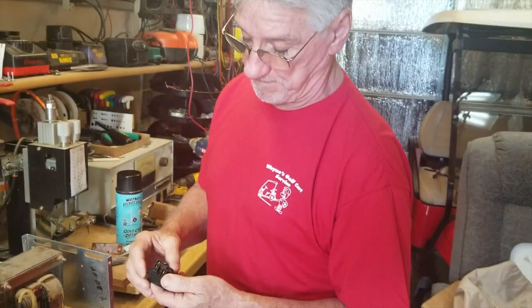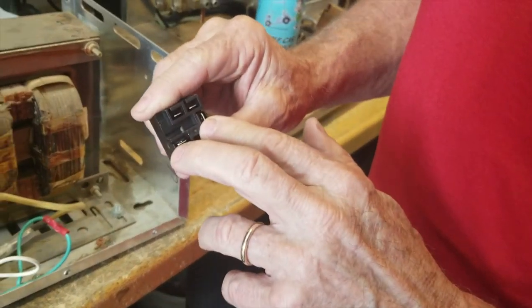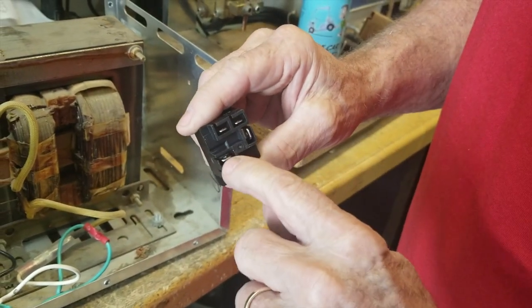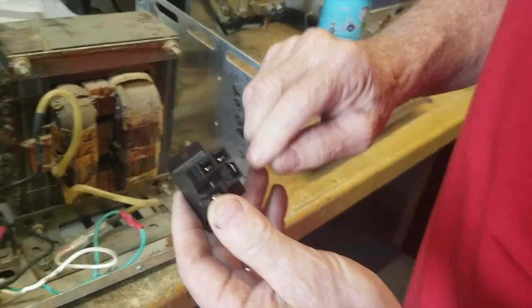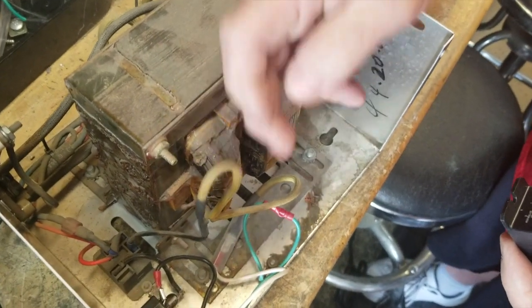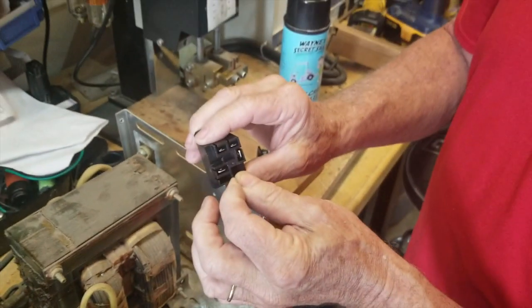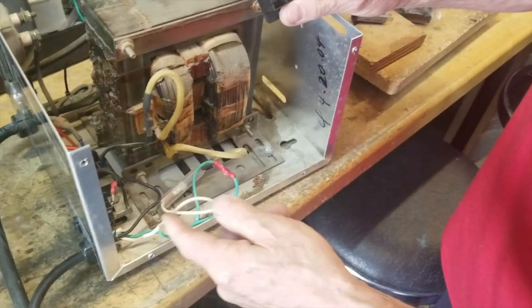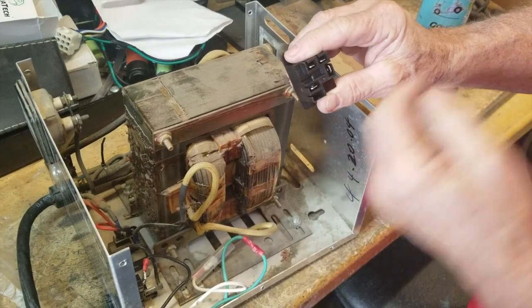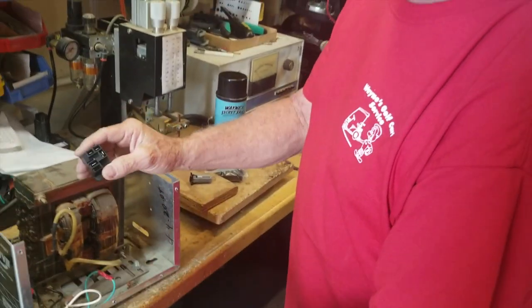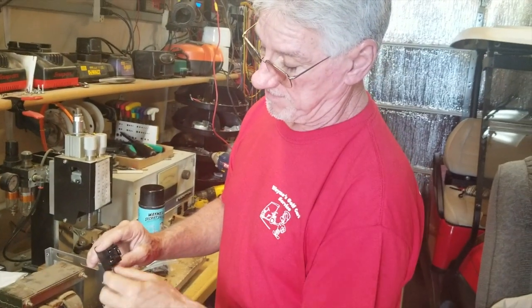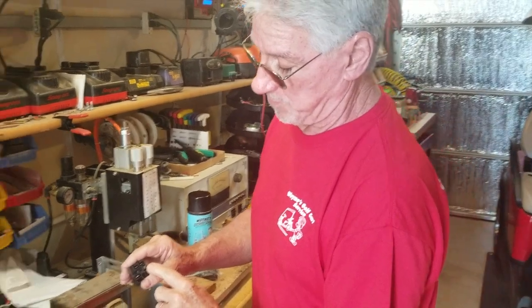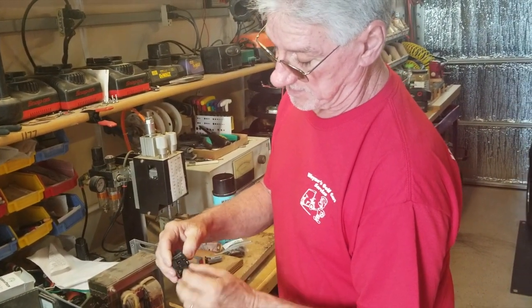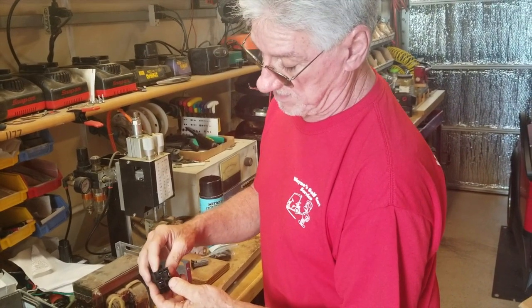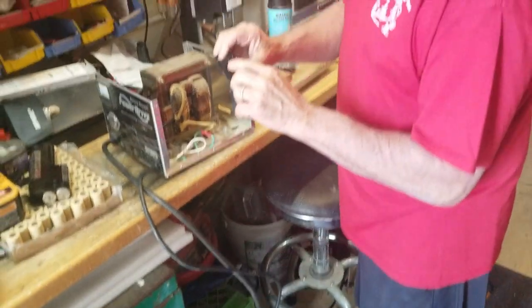I have one here. This is what the relay looks like. It's a 48 volt relay. These 2 big tabs are the contacts, which I said are normally open. From your breaker it goes to here, and from the other side of that it goes right to the transformer. That's this wire. If you were to close those, it would send power. If this was plugged in, it would send 110 volts directly to the primary side of this coil. That's what you want. The whole time this is plugged in, the relay is going to have 110 volt potential right there. It just will not go through until this closes. And what closes it are these 2 tabs here. That's the coil of the relay. Now, the coil is 48 volt.